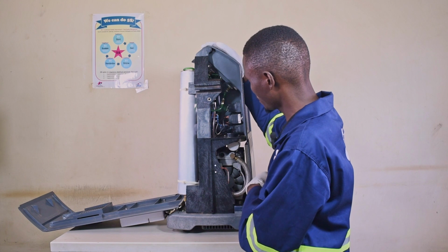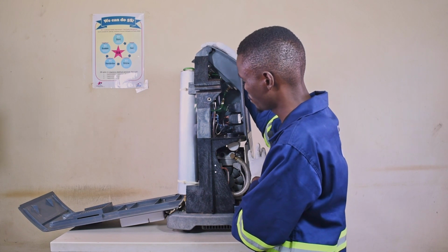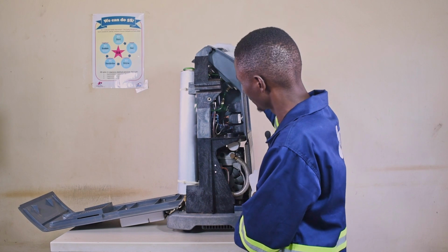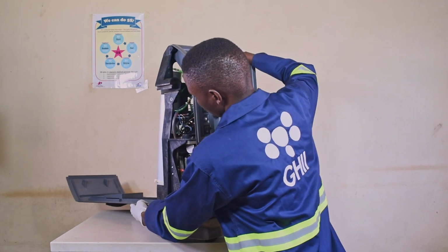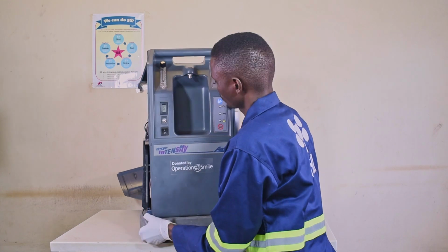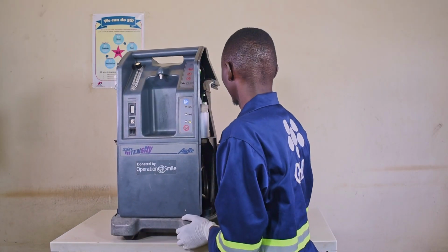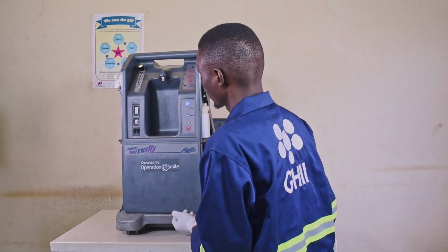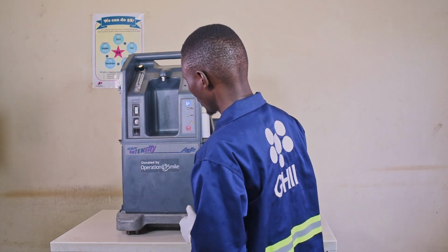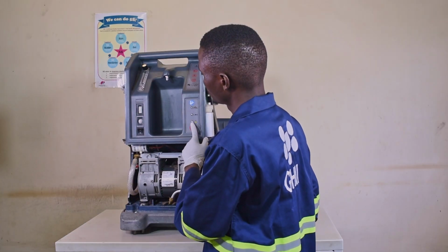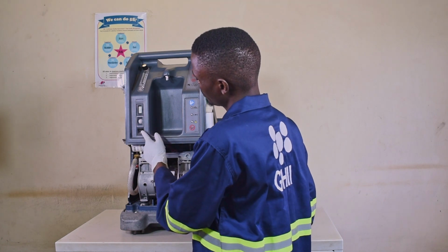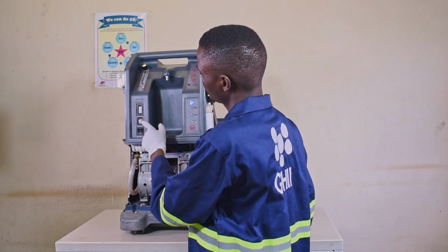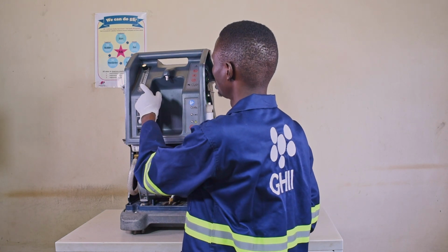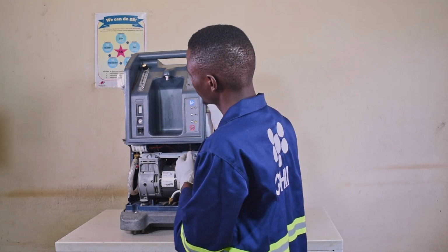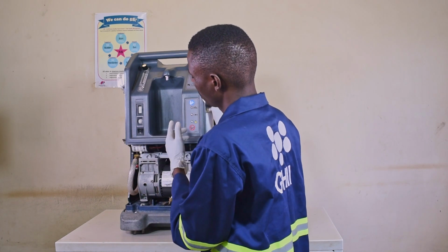For us to access the other internal components, we will have to remove the front covers of the unit. So I will remove the bottom cover. The top cover has many connections on it. There is the power switch, the circuit breaker reset button, the digital hour meter, and the flow meter. So we'll have to disconnect all the connections to the flow meter, the switches, and the hour meter.